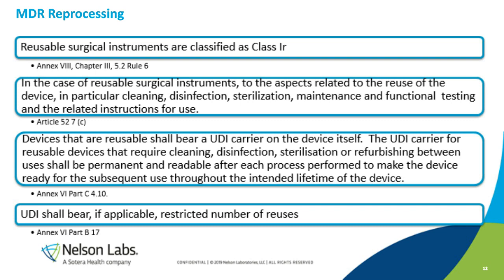Devices that are reusable shall bear a UDI, unique device identification carrier on the device itself. The UDI carrier for the reusable devices that require cleaning, disinfection, sterilization, or refurbishing between uses shall be permanent and readable after each process performed to make the device ready for subsequent use throughout the intended lifetime of the device, and the UDI shall bear, if applicable, the restricted number of uses. So once this is in place, it'll be easier to define the number of reprocessing cycles that can occur on each device.